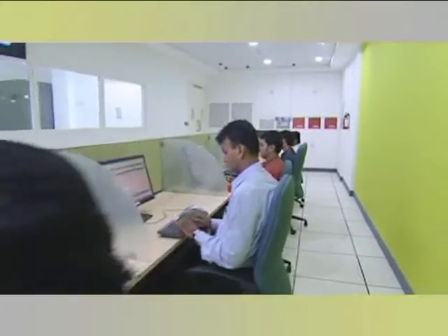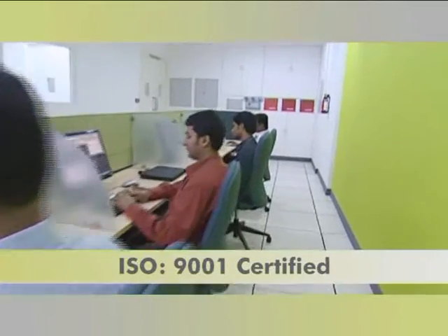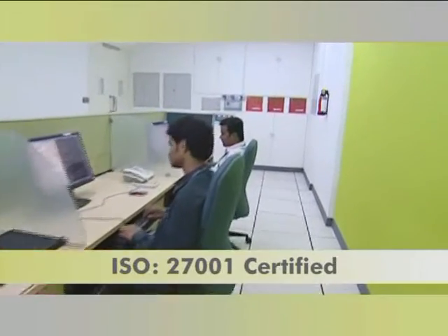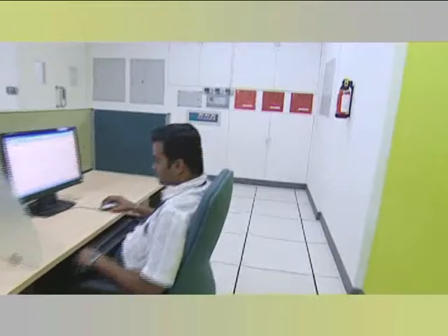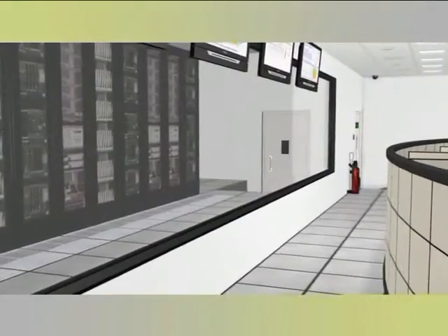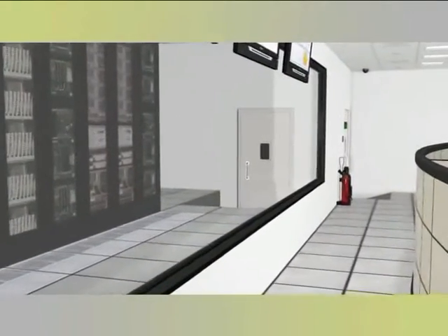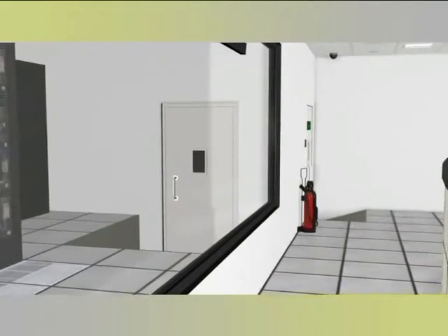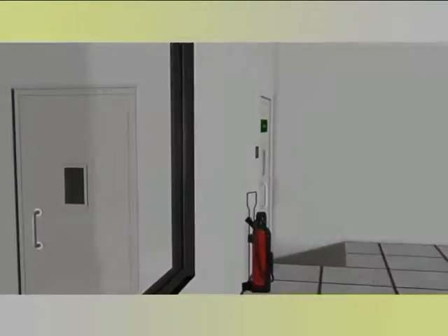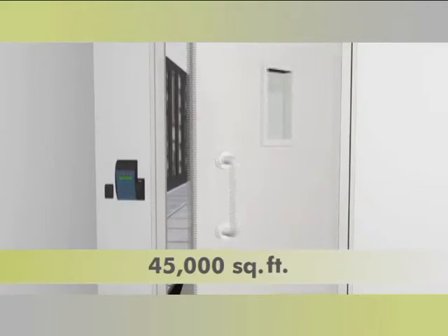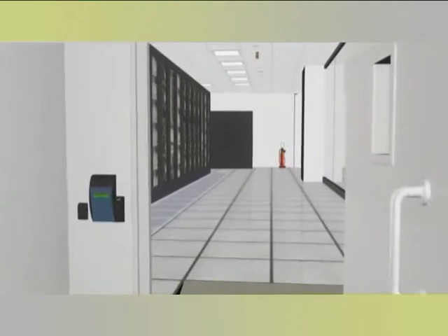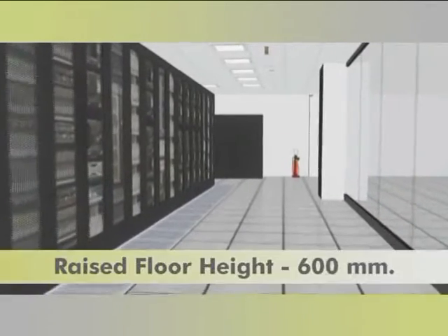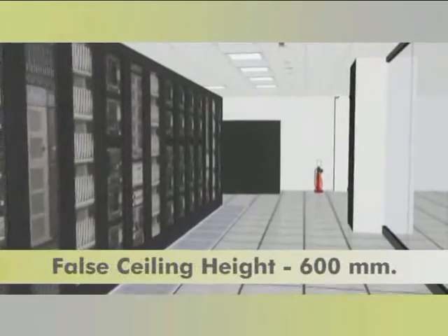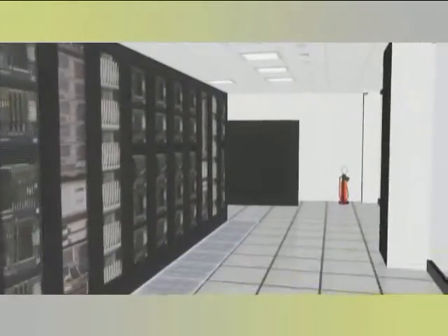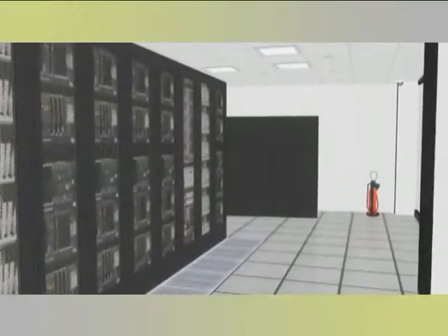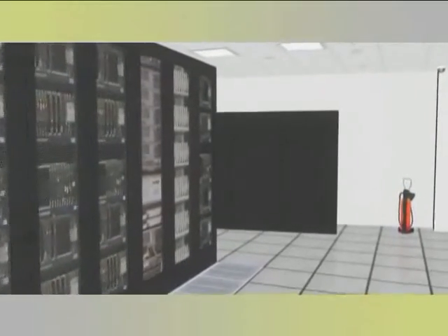Our data center processes adhere to ISO 9001 quality standards and with ISO 27001 for information security management. An online portal facilitates reporting of critical information on parameters like temperature, cooling, humidity, and SLA tracking. The server halls span 45,000 square feet and are divided across various modules. Raised floor height and false ceiling height for the data center is 600 millimeters. These are specifically designed to meet high-density power and cooling requirements.